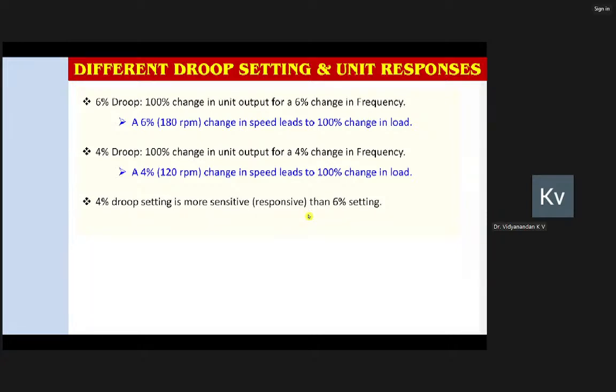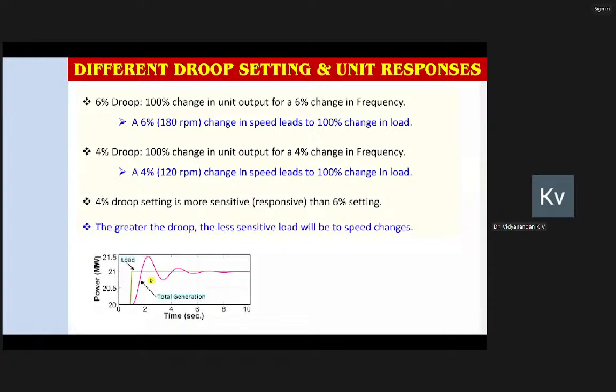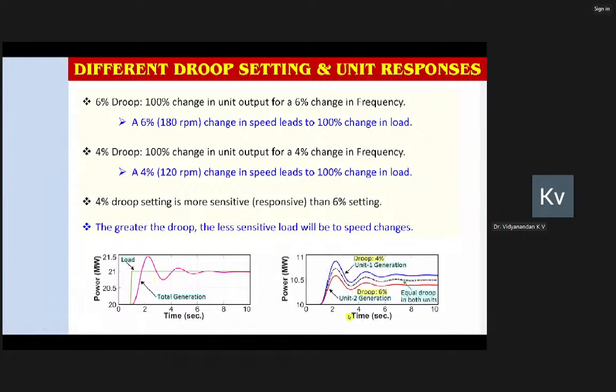For example, if you have two machines with say 4% and 6% droop, when there is a change in load, the machine with the lesser droop will contribute more, and the machine with the larger droop will contribute less. So that way, droop is also responsible for load sharing. Another role of the droop is proper load sharing between the units. Suppose you have 10 units in your power plant. How will these 10 units share their load whenever there is an extra demand for power and frequency falls? That you can correct by tuning the droop.